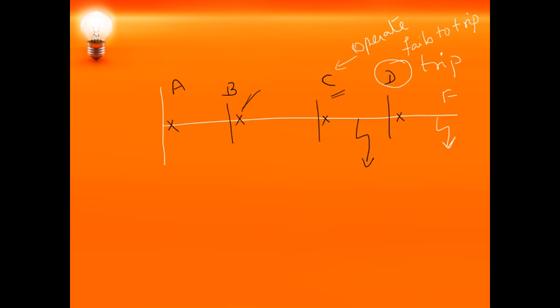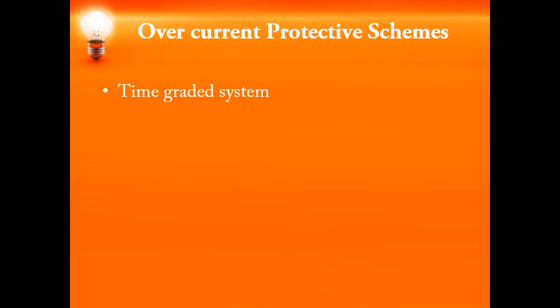We will see them one by one. The first one is a time graded system. In a time graded system, we set a timing unit for each of the circuit breakers used. For this time graded system, the type of relay used is the definite time overcurrent relay. Definite time overcurrent relays are used wherever you need a time graded system. In a definite time overcurrent relay, irrespective of the magnitude of the fault current, the circuit breaker will trip at the same preset time.